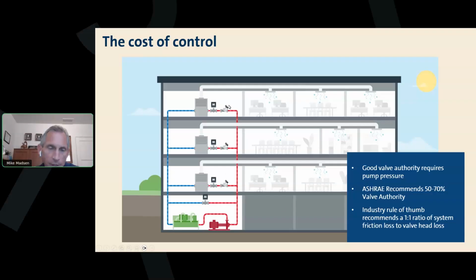So here I'm showing a conventional variable primary system again: primary pump, chiller, bypass, air handler units, 3 motorized control valves. A 50% valve authority means that the pressure drop through this top valve by that top air handler is equal to all the other pressure drop in that zone. So all my piping friction, my pressure drop through my coil, all my fittings, all my return piping: if the pressure drop of the valve is equal to all that other piping loss, that's a 50% valve authority.